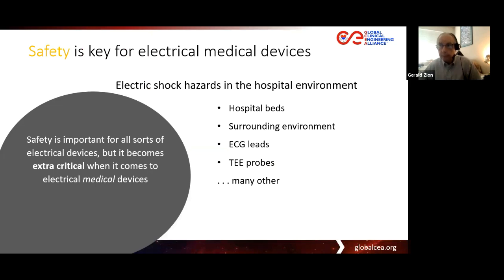Hospital beds, surrounding environment, leakage tests for ECG, transesophageal echocardiographic probes, because those transducers image from right behind the heart, in the esophagus outward, and the voltage available, the electromotive force available behind the face of the transducer is 400 to 800 volts. Certainly more than enough, even with a small resistance, to provide current flow that would overwhelm the heart's own pacemaker activity and drive the heart into fibrillation. So these are really important things. Your hospital biomed department may not do hospital beds, electrical beds, but someone is doing it. You may not do surgical tables, but somebody is doing it. And it's the responsibility of the biomed department to make sure that those records are kept.